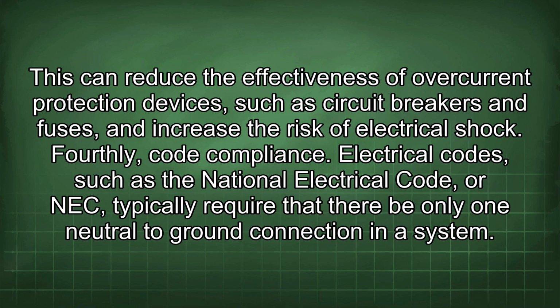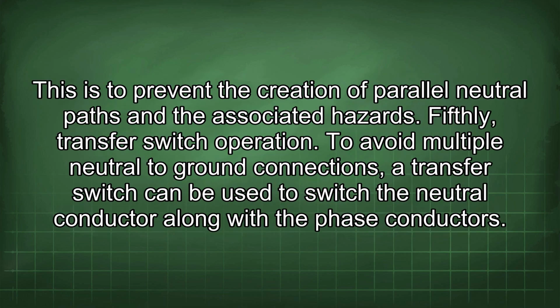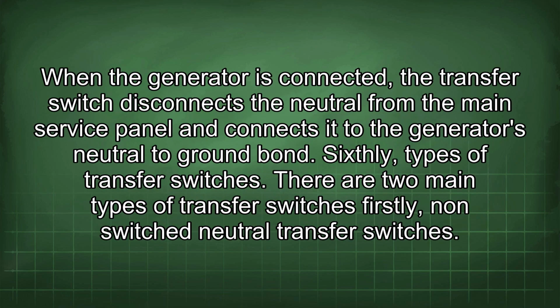Electrical codes, such as the National Electrical Code, or NEC, typically require that there be only one neutral to ground connection in a system. This is to prevent the creation of parallel neutral paths and the associated hazards. Fifthly, transfer switch operation. To avoid multiple neutral to ground connections, a transfer switch can be used to switch the neutral conductor along with the phase conductors. When the generator is connected, the transfer switch disconnects the neutral from the main service panel and connects it to the generator's neutral to ground bond.